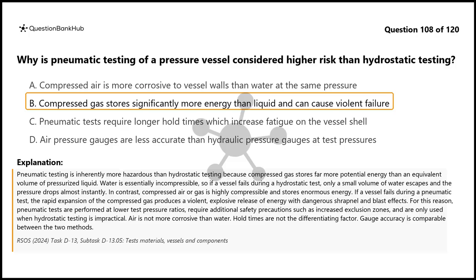In contrast, compressed air or gas is highly compressible and stores enormous energy. If a vessel fails during a pneumatic test, the rapid expansion of the compressed gas produces a violent, explosive release of energy with dangerous shrapnel and blast effects. For this reason, pneumatic tests are performed at lower test pressure ratios, require additional safety precautions such as increased exclusion zones, and are only used when hydrostatic testing is impractical. Air is not more corrosive than water. Hold times are not the differentiating factor. Gauge accuracy is comparable between the two methods.